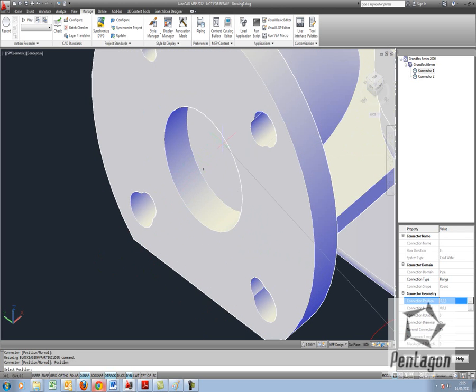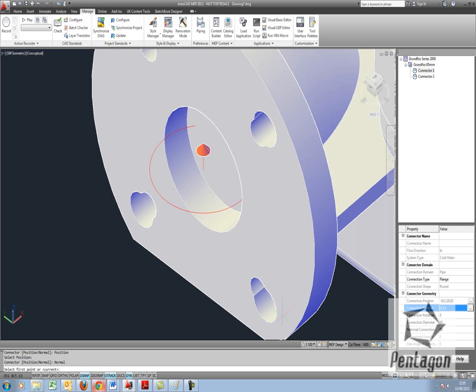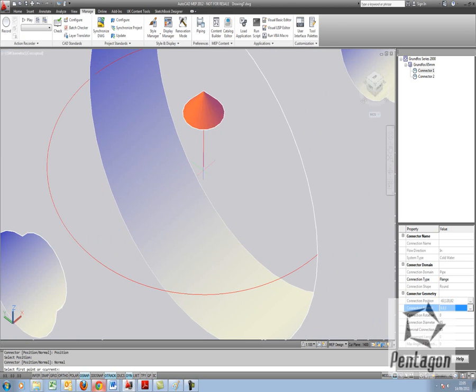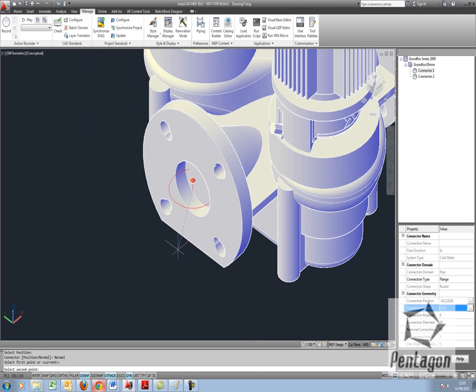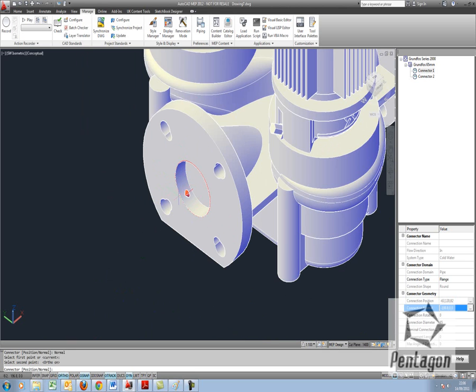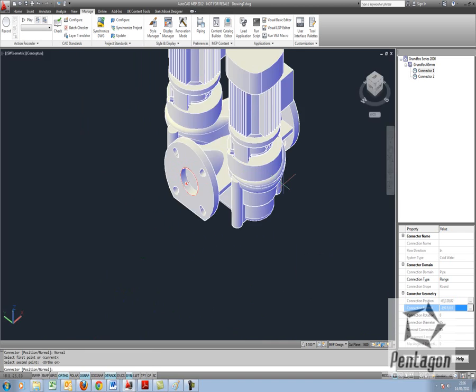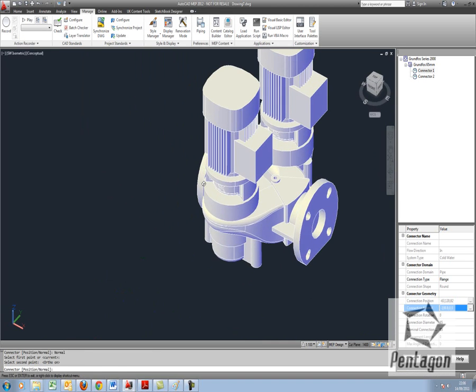So you can see there's a default position down here. That's not what I want. I physically want it on the centre point here. But note the direction. It needs to be facing out. So once we've put the connection position in, we can go to the connection normal. If I click on the button, I can hook in, pick the insertion point, and I'm going to bring out my ortho. So it's out 90 degrees like so. So you can see there's my connection.